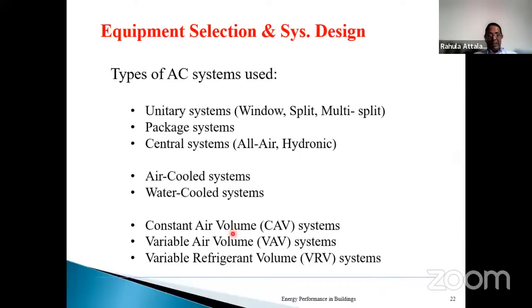Then when it comes to the air supply, we also have constant supply of air, what we call constant air volume, or variable supply of air, where the air flow rate can be varied depending on the load condition. This appears to be more efficient than that, but the cost will be higher. And we also have a new variant, or not really new, some time back, but with subsequent evolution, what we call the variable refrigerant volume. So instead of having the prime mover or the compressor changing according to the load, in addition, they're trying to very precisely control the refrigerant flow to meet the load requirement, which is efficient operation, and it's a recent development compared to the other variations.